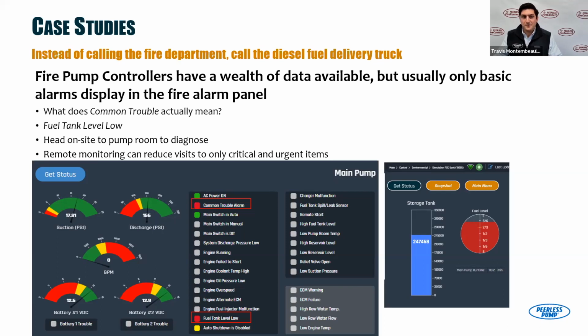So you probably got to go out and maybe go buy another battery or call a controller manufacturer and get new chargers if you got a charge problem, whatever. Point is you can reduce those visits if you know ahead of time what the actual situation is. And so this is that data that you get from a Modbus enabled fire pump controller. We get the fuel tank level low, the ECM warnings, and the high oil, the low oil pressure and the high fuel tank level, and all those alarms that typically would present as a common trouble alarm.